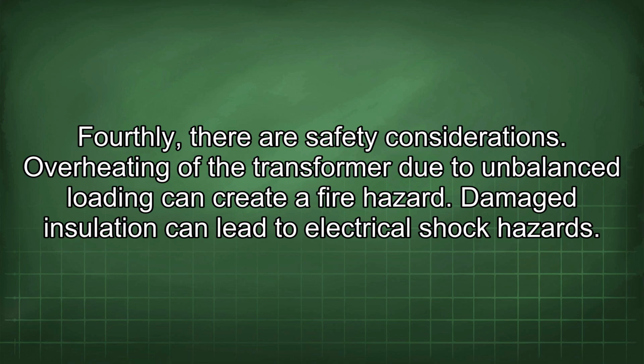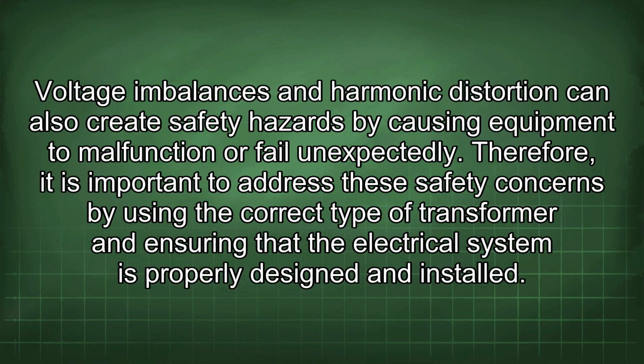Fourthly, there are safety considerations. Overheating of the transformer due to imbalanced loading can create a fire hazard. Damaged insulation can lead to electrical shock hazards. Voltage imbalances and harmonic distortion can also create safety hazards by causing equipment to malfunction or fail unexpectedly. Therefore, it is important to address these safety concerns by using the correct type of transformer and ensuring that the electrical system is properly designed and installed.